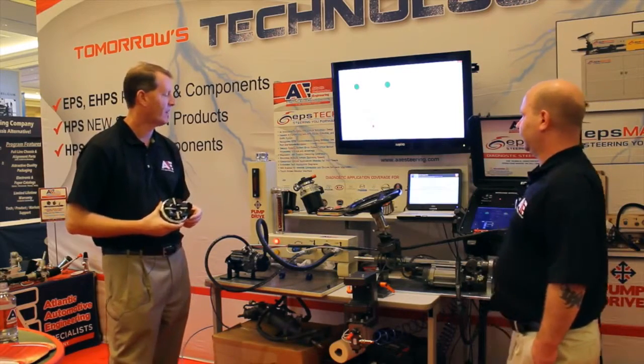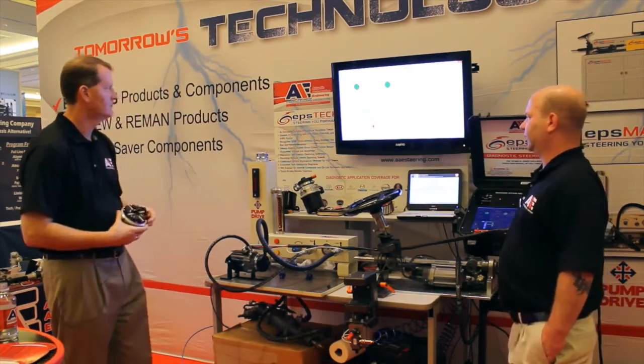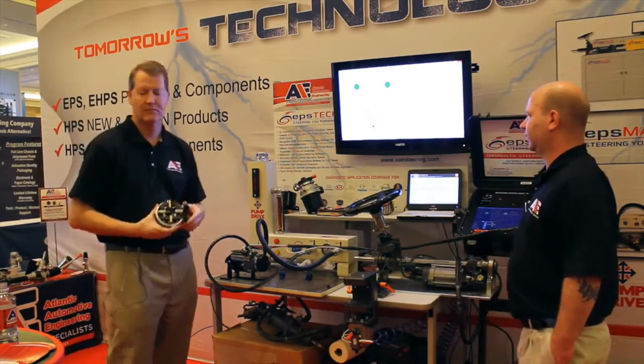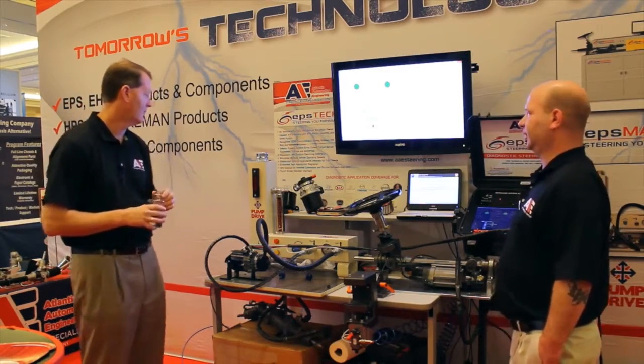Right now it's running into different cycles. You can run typically 5 cycles. You have a load time and you have a rest time, and you have the cycle ignition. So you can basically plug and play, set up, and it'll automatically test the pump. You don't have to be standing over it and watching it or anything like that. You can multitask with it by repairing another unit or setting up to test another unit.